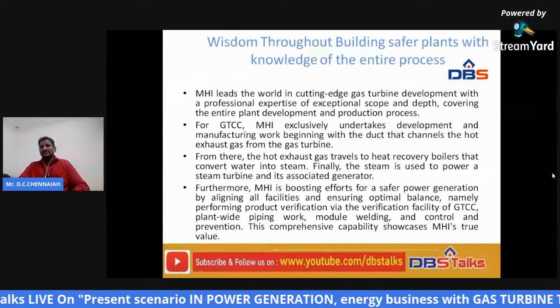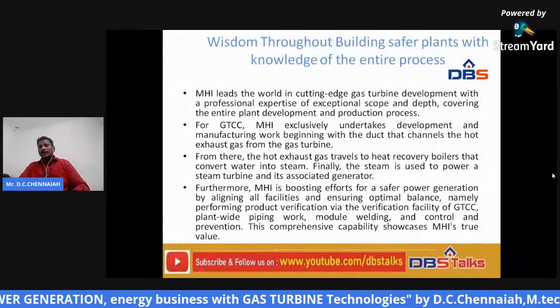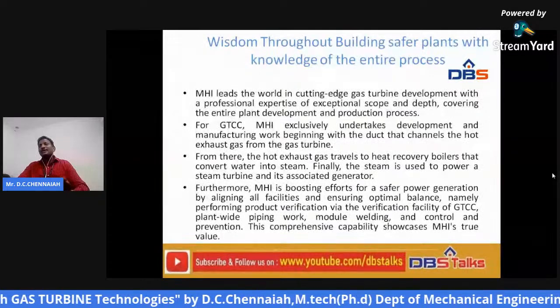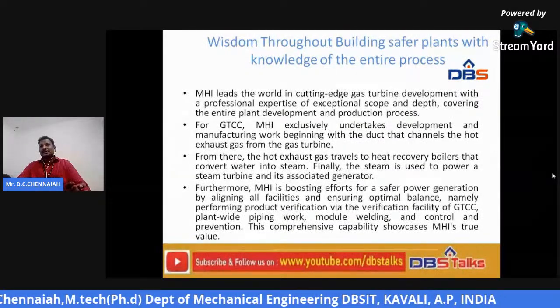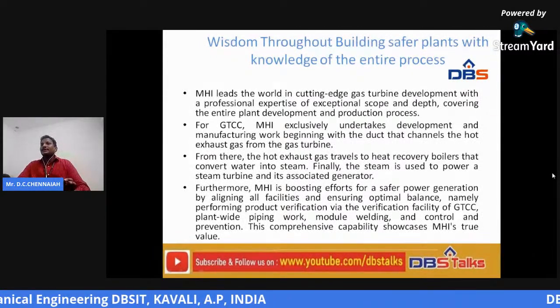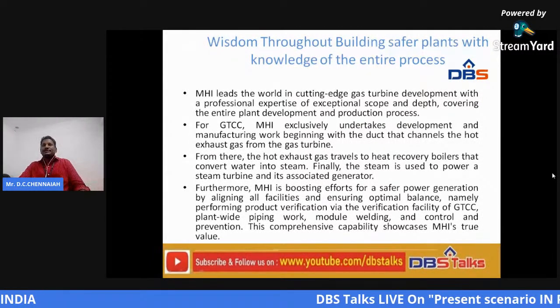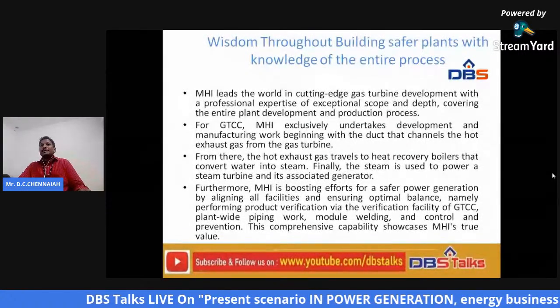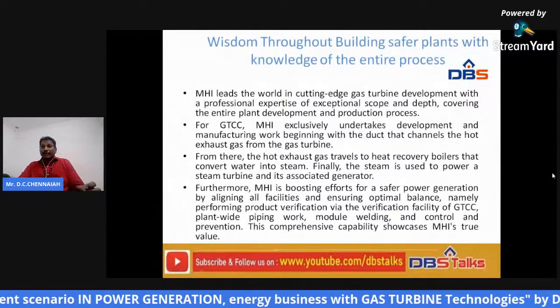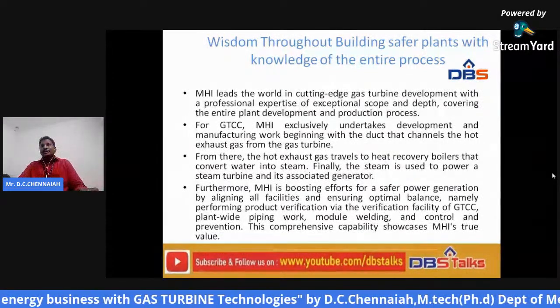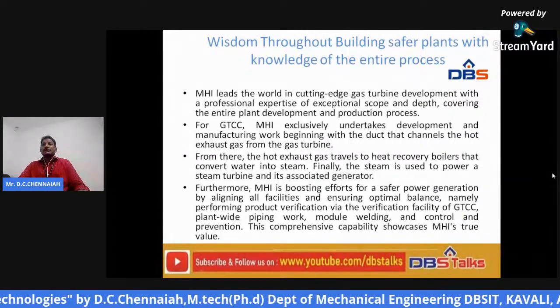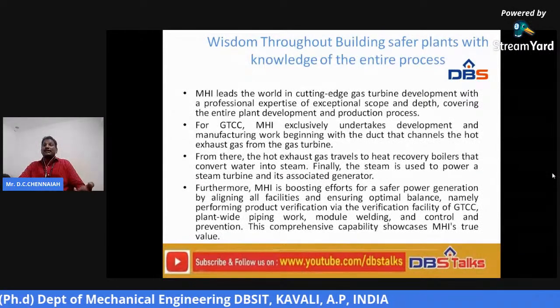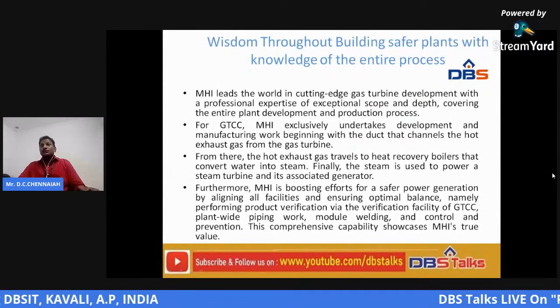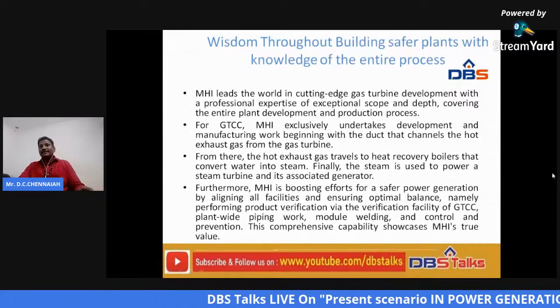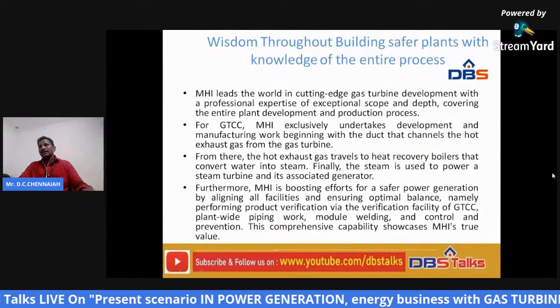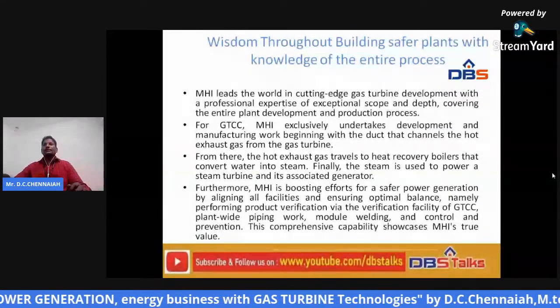So as the temperature difference is there, there is very much chance for the loss of heat from the hot gases to the environment. If you are losing certain heat, we are getting less production of steam. If the mass flow rate of steam is less, the power produced by the steam turbine will be less. So we have to protect the heat by applying proper thermal insulation to the duct which carries the hot gases from the gas turbine to the heat recovery steam generation boiler or heat exchanger. In the next coming slides, we will discuss the line diagram.